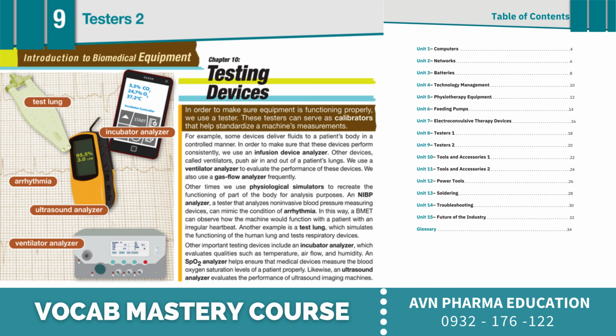Another example is a test lung, which simulates the functioning of the human lung and tests respiratory devices. Other important testing devices include an incubator analyzer, which evaluates qualities such as temperature, airflow, and humidity. An SpO2 analyzer helps ensure that medical devices measure the blood oxygen saturation levels of a patient properly. Likewise, an ultrasound analyzer evaluates the performance of ultrasound imaging machines.